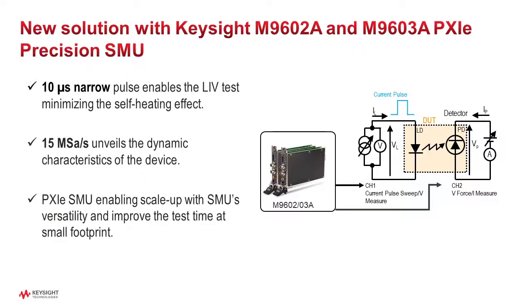With the new solution of M9602A and M9603A PXIE Precision SMU from Keysight, it offers 10 microsecond narrow pulses, which enables the LIV test with minimized self-heating effect.